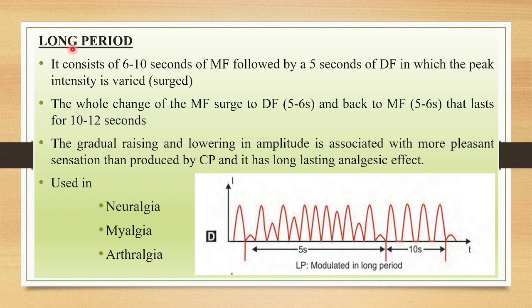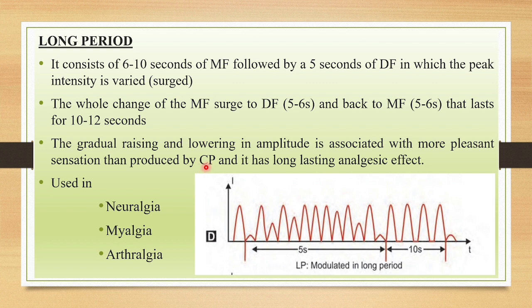In this diagram you can see one second of diaphase and one second of monophase. The next mode is long period or longest period. It consists of 6 to 10 seconds of monophasic followed by 5 seconds of diaphase in which the peak intensity is varied. The whole change from monophasic surge to diaphase takes 5 to 6 seconds, and back to monophasic lasts 10 to 12 seconds. The gradual raising and lowering in amplitude is associated with more pleasant sensation and it has a long-lasting analgesic effect.